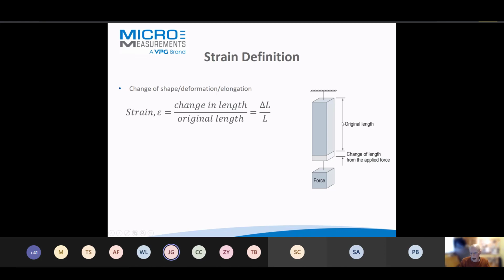If we had a change of length equal to the original length - for example, a 100 millimeter length stretched by a further 100 millimeters - we would have one strain. Obviously most materials don't go to one strain, so we often talk about microstrain, which is invisible - we can literally measure the invisible. One microstrain is 0.000001 units per unit, whether that's meters per meter or inches per inch. Think of a meter rule: 1 micron in a meter is 1 microstrain, micron being a millionth of a meter. If you calculate that down for a typical 6 millimeter gauge, we're talking about measuring 6 nanometer changes.